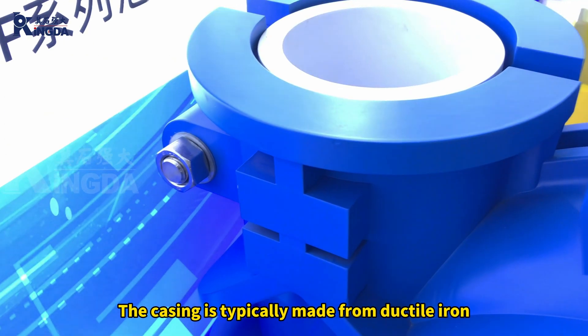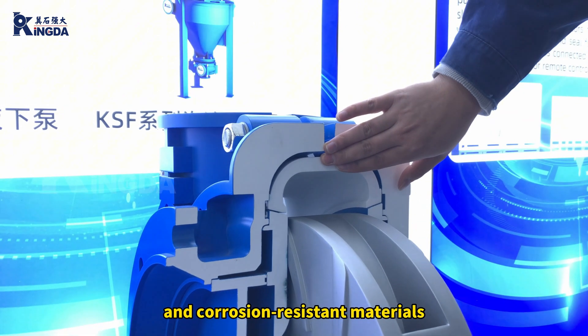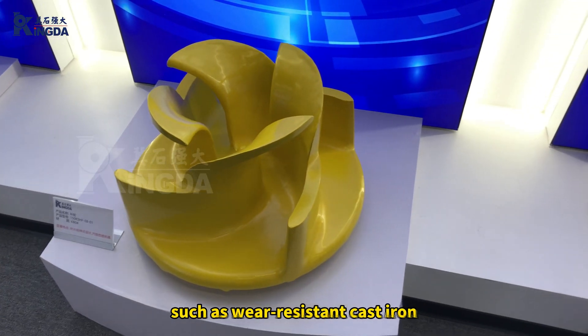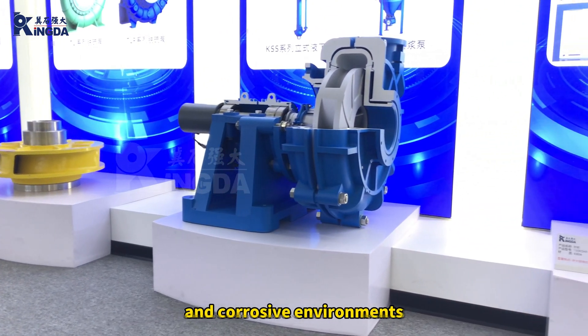The casing is typically made from ductile iron, which has excellent pressure resistance. Inside, we use wear-resistant and corrosion-resistant materials, and you can choose from different materials depending on your needs, such as wear-resistant cast iron or rubber materials, making it ideal for high abrasion and corrosive environments.